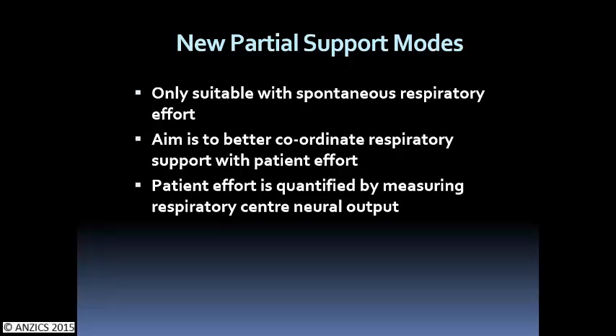Probably of the newer modes of ventilation, the two things that stand out, that are being pushed commercially, are proportional assist and NAVA, which are the servo, or whatever they're called now, whoever makes them. But the NAVA, the triggering of the ventilator by the electrical activity of the diaphragm, when that technology first came out, it was used experimentally in neonates, because neonates and small kids, our problem with ventilating them in any sort of spontaneous mode is that we can't get them to trigger properly. We can't get the ventilator to cycle.